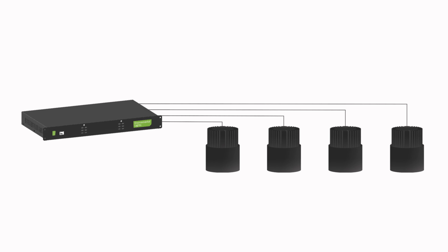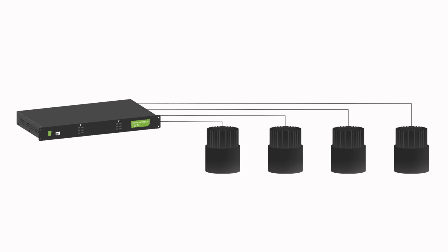So another advantage of putting the power supply in a remote location, how does that change the wiring requirements for the system? So what's really cool about this is that now rather than having 120 volts AC running throughout the building, where you require a wire that's capable of handling 1800 watts, we're putting all the high voltage stuff in a closet. And so what that does for us is we're able to shift from running 14/2 or Romex throughout a building to running low voltage cable that's all Class 2. So not only are we using a lot less copper, but it's a much safer installation.